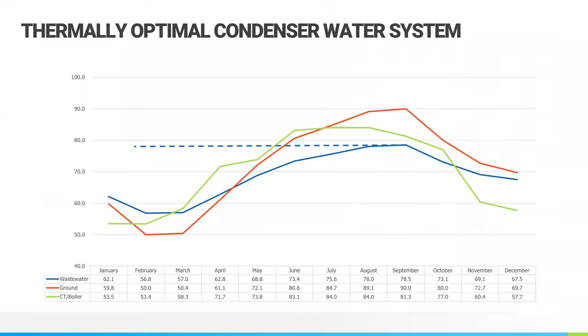So one of the other things that really came out of that system is, your ground source or water source heat pump systems operate on a temperature range. And that range of temperatures is directly associated with the efficiency of that equipment. So the less you can have that range vary, and especially the more you can decrease its relative low and high peaks, the more energy efficient that system's going to be.